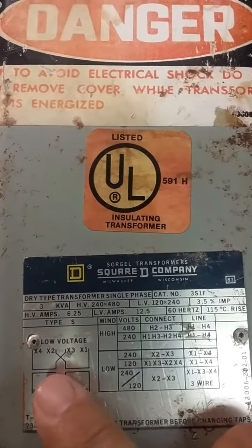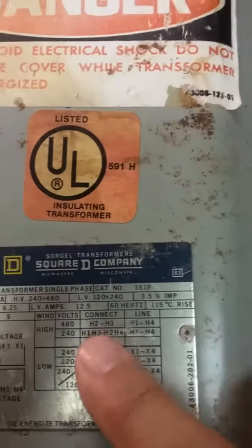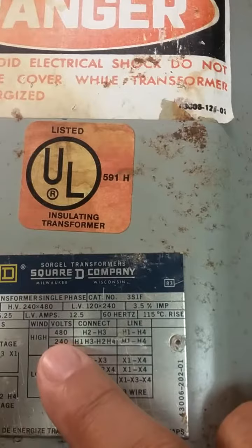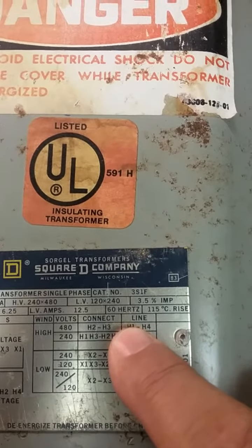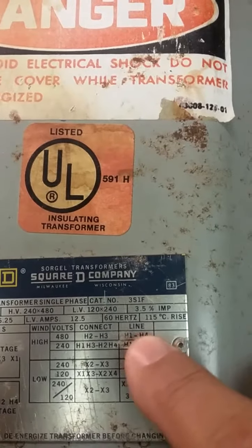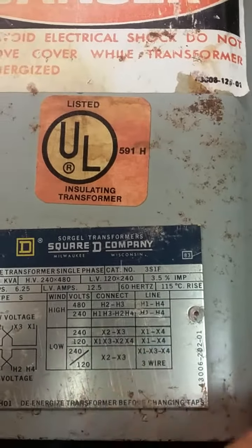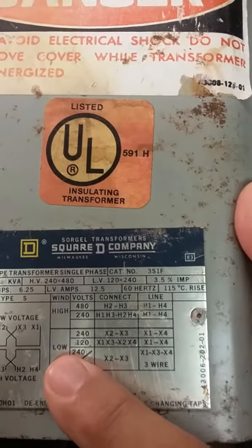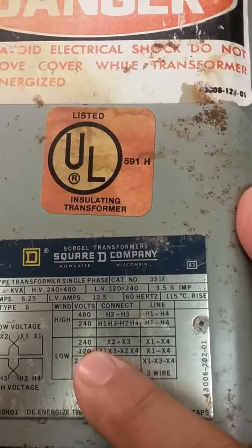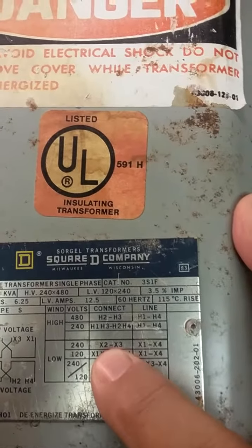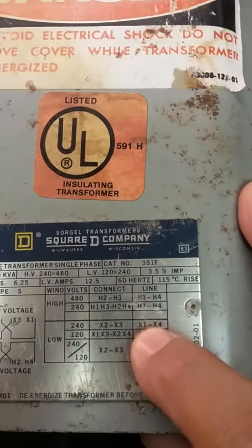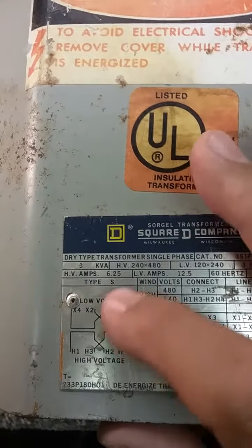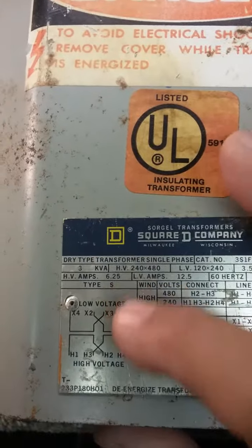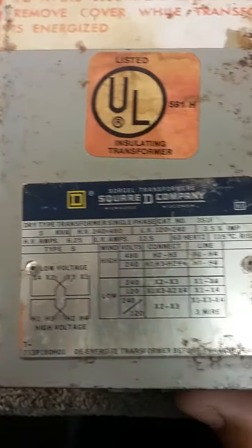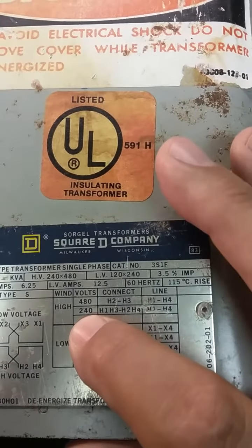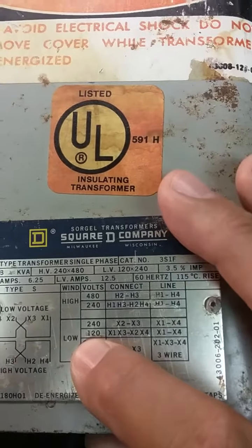Of course, you can separate these, and you can have different options. So you can put 480 across the entire thing by tying H2 and H3 together and running the line coming in to H1, H4. Or on the output, you would get 240 if you tied in X2 and X3 and put the load on X1 to X4. So basically, it's a half step down. Whatever you put in on the primary, you're going to get half as much voltage on the secondary. So if you put 240 in on the primary, you get 120 on the secondary.